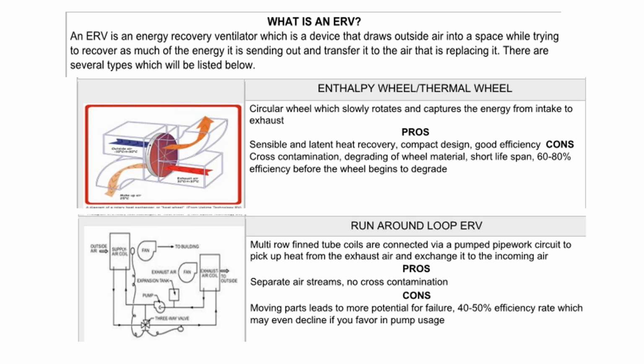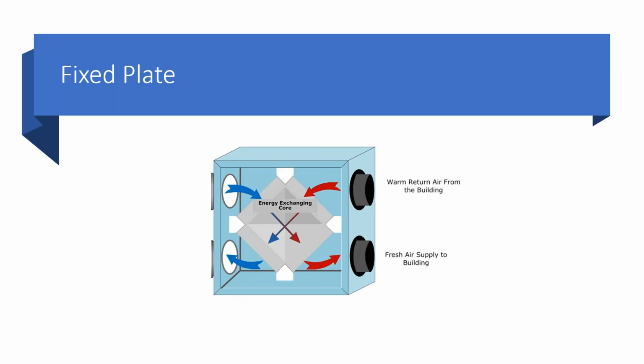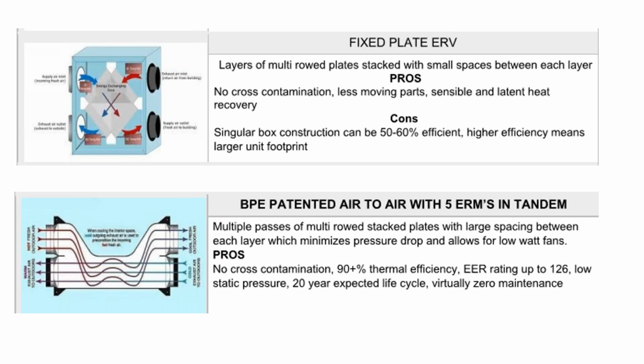Runaround loop is another old school way of doing it. There are a lot of moving parts and separate air streams. The positive is there's no cross-contamination because they're completely separate, but there are a lot of moving parts, so a lot of people don't opt for this style. Then we go into the fixed plate styles, where the warm air from the building and the fresh air supply go through the same space but never actually touch one another, because they're in individual spaces through the energy exchanging core.